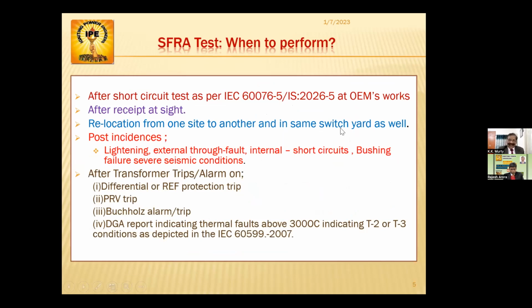Relocation from one site to another site in the same switchyard as well. When you are relocating from one site to another, there is every possibility of jerks or thrust which the transformer may experience. Post incidences: lightning, external through fault, internal short circuits, bushing failure, severe seismic conditions, etc. After the transformer trips or alarm on differential or REF protection, PRV trip, Buchholz alarm trip, DGA report indicating thermal faults above 300 degrees centigrade, indicating T2, T3 conditions as depicted in IEC 60599. T3 is more than 700 degrees, and T2 is more than 300 degrees. This is a degree sign. Actually, it looks like a 0. So please read it as degree.